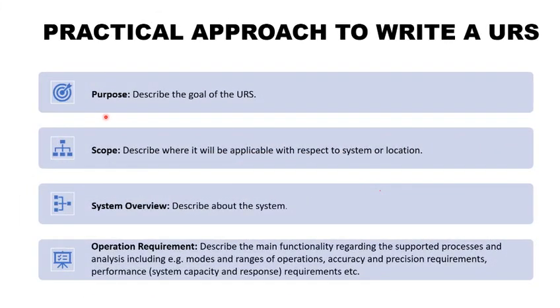Regarding the practical approach to write a URS, the first point is purpose — describe the goal of the URS, defining what kind of operation, function, regulatory, and performance requirements are expected from the system. Next is scope — describe where it will be applicable with respect to the system or location. For example, if the system will be used in a particular department, specify the location.